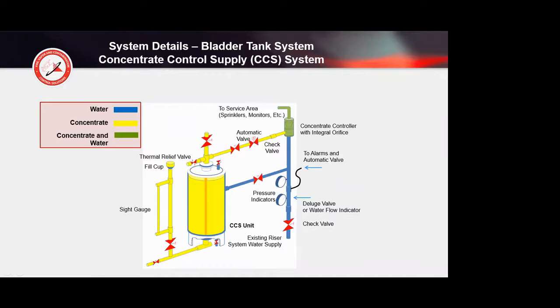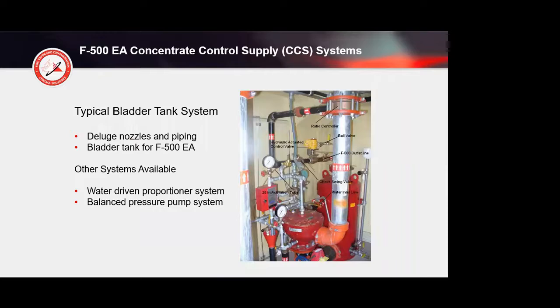The agent would be proportioned in at a most, we typically just use 1% for Class A materials, like the composite material in Brazil was 1%, rubber tires here in North America, 1%. And then for flammable liquids, we would use a 3%. For lithium ion battery, 3%. And for Class D is 3%. So the ratio controllers that we have range from 2-inch up through 8-inch with orifice sizes for either a 1% or a 3%. So this is showing better the different systems here.